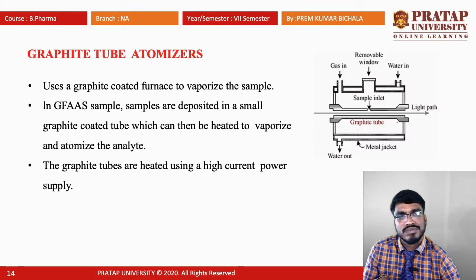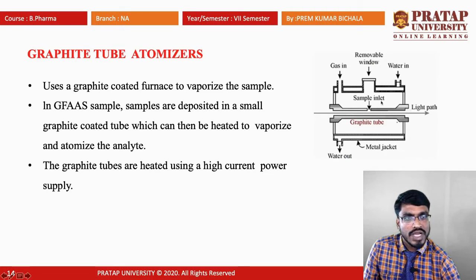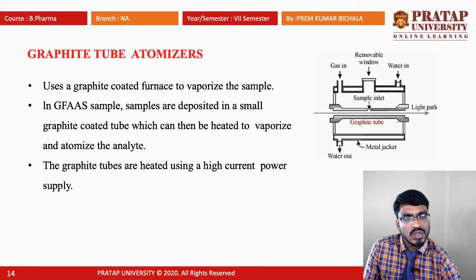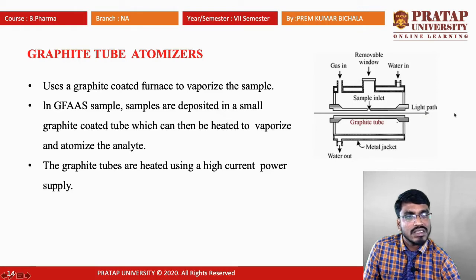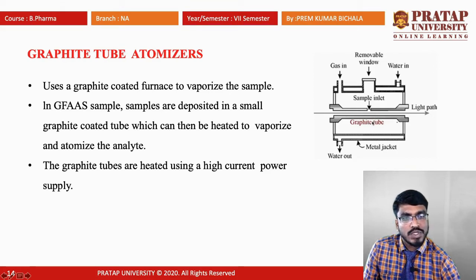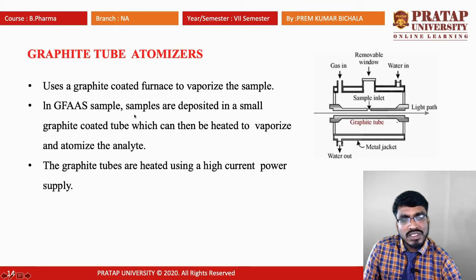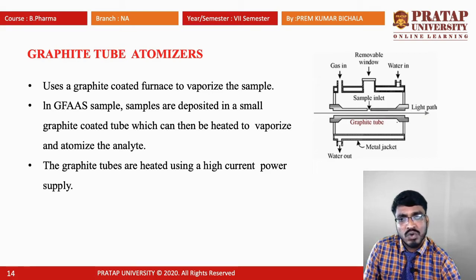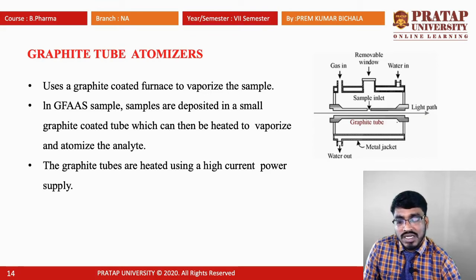This is the graphite atomizer. Here we have a sample inlet from which the sample is inserted. There are two inlets: a gas inlet and a water inlet. The green color arrow shows the light path, and at the bottom of the light path we have the graphite tube, along with a metal jacket. It mainly uses a graphite-coated furnace to vaporize the sample. In the graphite tube atomizer, samples are deposited in a small graphite-coated tube, which can then be heated to vaporize and atomize the analyte. The graphite tubes are heated using a high-current power supply.